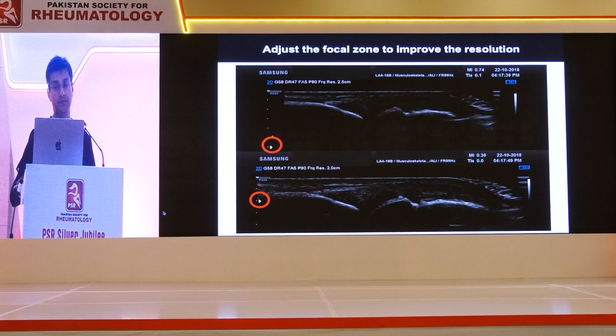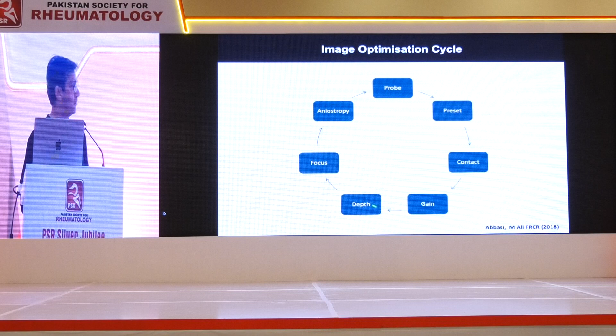So making sure that the depth is appropriate and that the focus is appropriate. And then finally, we come to anisotropy. If you've done all of these things, you've got the right probe, the right preset, the contact is good, you've adjusted the gain appropriately, your depth is good, your focus is good. If you're still getting an ugly image, then it might be because you're doing something called anisotropy.